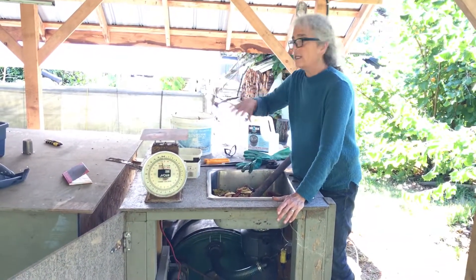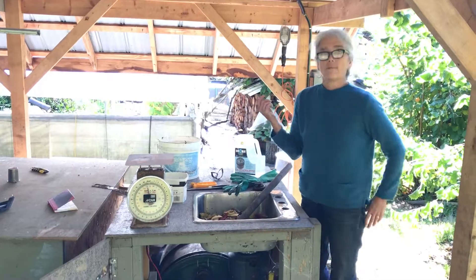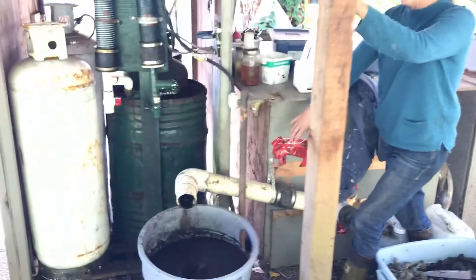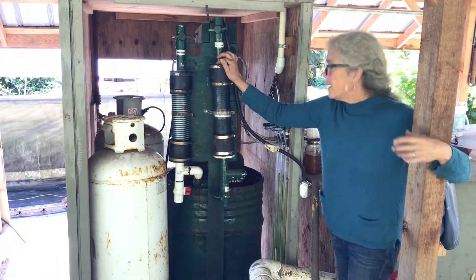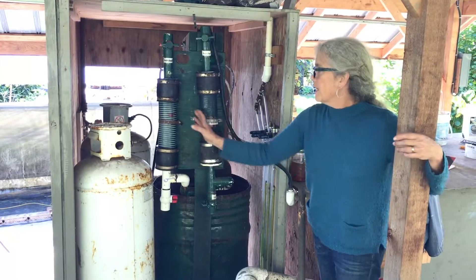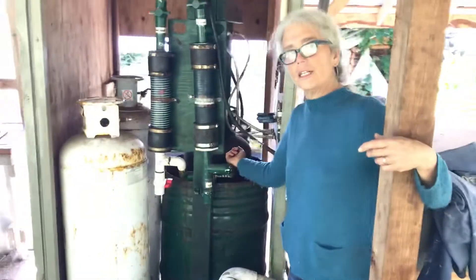This tank is completely enclosed with heat cables wrapped around it and insulation around that, kept between 32 and 38 degrees centigrade — that's where the gas builds up. The gas comes out of a hose right over here. This is completely airtight — this is the anaerobic digester in this container. The gas is purified: it runs through a carbon material which removes the hydrogen sulfide, then through calcium carbonate that de-waters the gas.